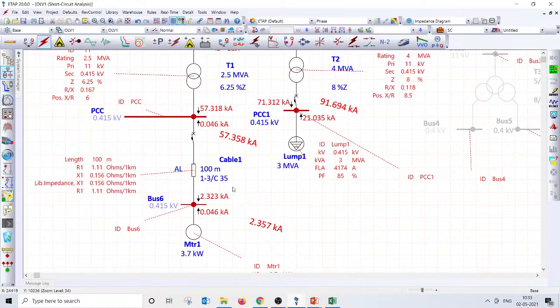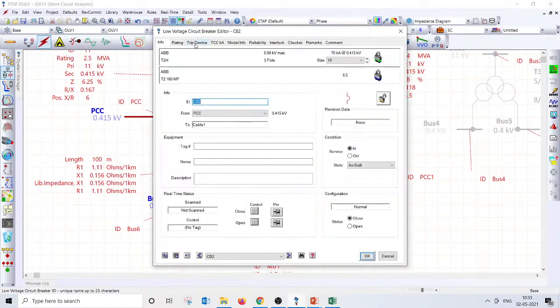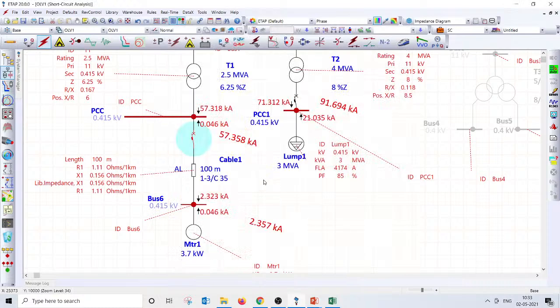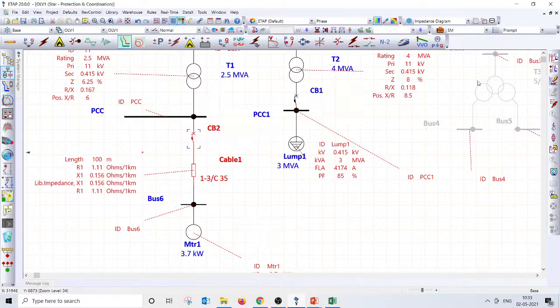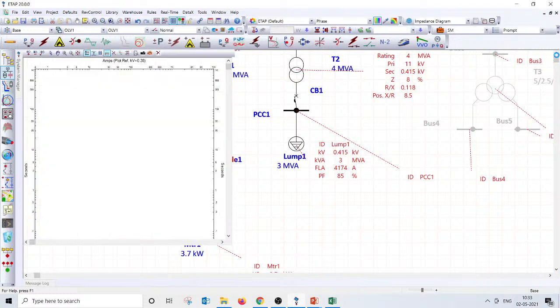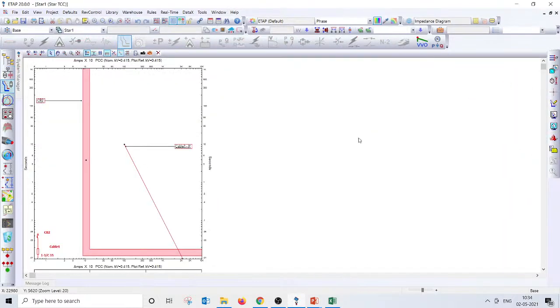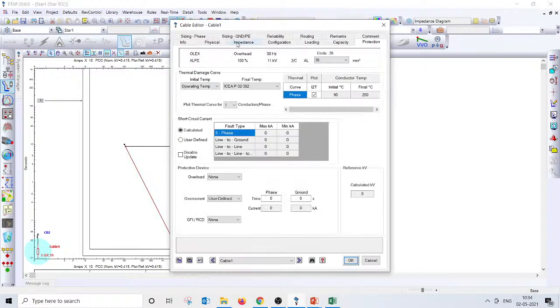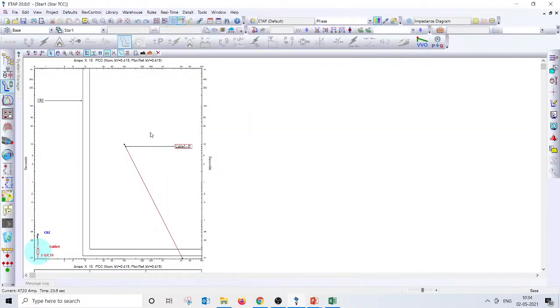And the third important aspect: let's give some setting for this, and then let's see whether this device is able to protect the cable or not. We have given some settings already, so let's go forward and look at it, right? This is the 35 square cable which we have selected, but try with maybe a 2.5 square cable or a 4 square cable. The damage curve will be much lower, and your protection may not be able to safeguard your cables.